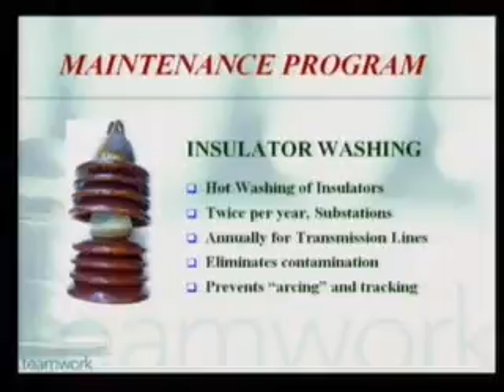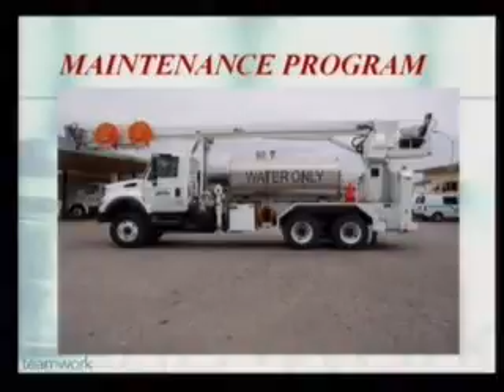We have invested in equipment where we use distilled water at high pressure, about 650 psi. It's on a boom, gets up to the insulator, and actually hot washes the insulators. Again, that prevents any arcing or any failure on our overhead systems. And we have a lot of contamination here in Glendale, just coming off the freeway. The PM10s, all that stuff accumulates and attaches to the insulation.